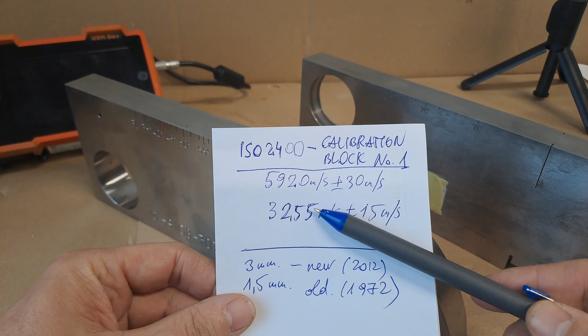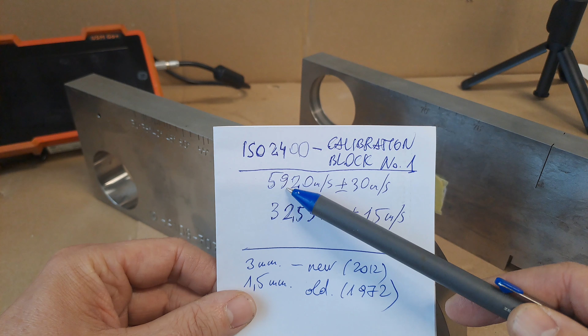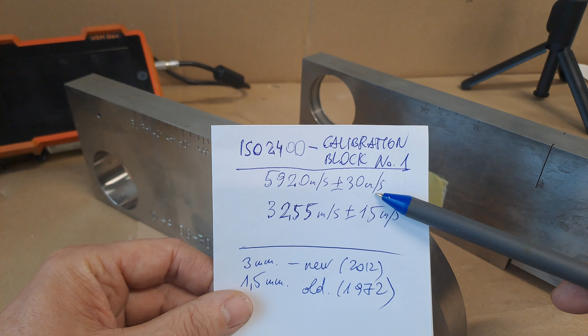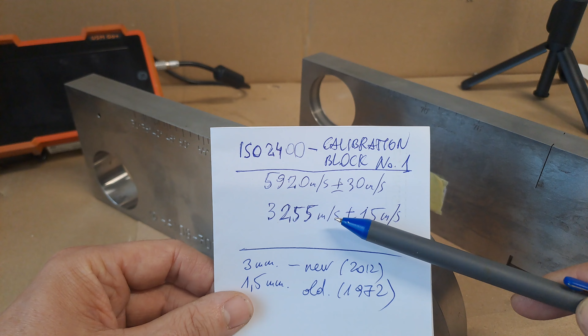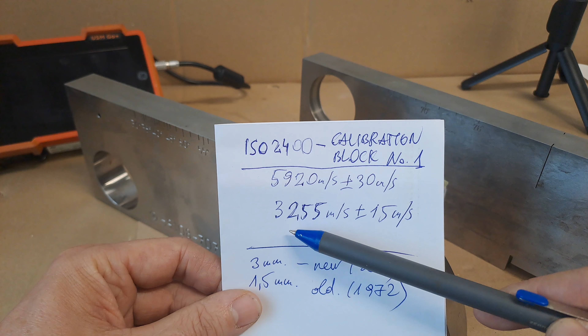The standard is for calibration blocks number 1, and the velocity of sound in these blocks is 5920 plus minus 30 and 3255 plus minus 15. So when we calibrate with these blocks, we can put in these numbers, or if we use auto calibration, we can just leave them as they are, but I wouldn't use them as they are.